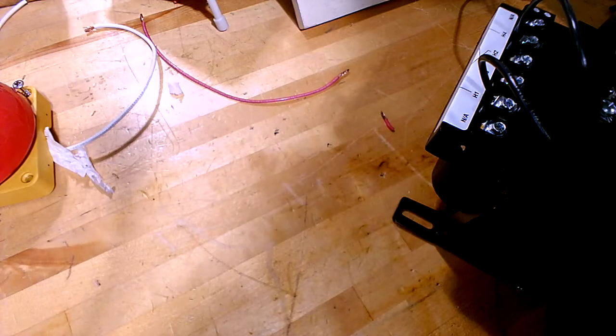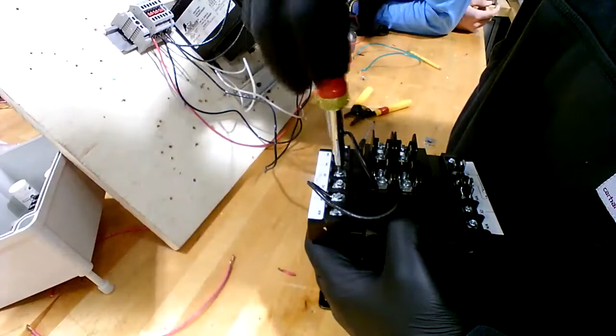That's what you call configuring the transformer. You configure it for low voltage or high voltage. You have to decide when that thing comes out of the box: does your machine run on low voltage 240, or does it have 480 coming in? They make dual voltage universal transformers so they'll work on a lot of different machines. The company doesn't have to make so many different model number transformers, or have one work for a bunch of different setups.